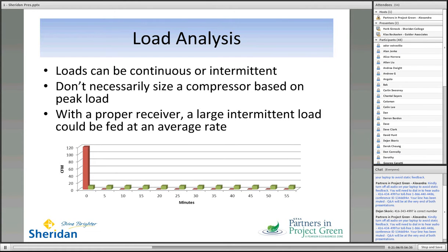Another point I'd like to raise, we're getting near the end of the things I'd like to present on the supply side, but there's a couple of last bits to pay attention to. One is that sometimes compressors are sized looking at a peak load requirement. If you have a load that's intermittent, it operates maybe 5 minutes out of an hour, you don't need a compressor necessarily that's sized to hit that peak. What you could do, and I've shown this in a very crude format, I wouldn't call it scientifically rigorous, but the point of the graph is to show the idea and the concept of spreading out the CFM requirement.